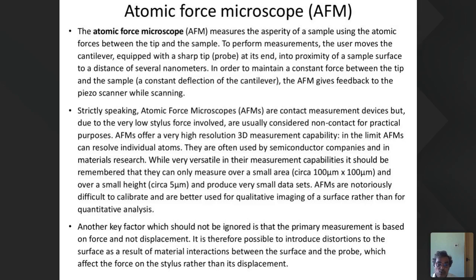To perform the measurements, the user moves the cantilever, equipped with a sharp tip probe at its end, into proximity of a sample surface, to a distance of several nanometers. In order to maintain a constant force, the AFM gives feedback to the piezo scanner while scanning. You are maintaining the constant force. Strictly speaking, AFMs are contact measurement devices, but due to the very low stylus force involved, they are usually considered non-contact. Though we say it is a contact, the force is very, very low, so practically we are taking it as a non-contact type.